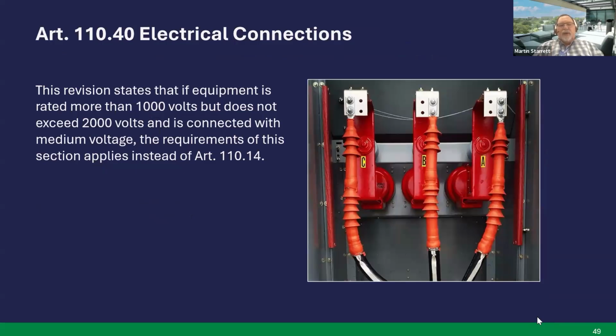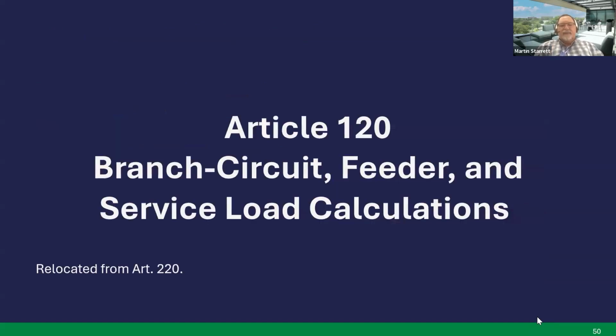Article 110.40, electrical connections. We already looked at 110.14, but 110.40 will apply if equipment is rated more than 1,000 volt, but does not exceed 2,000 volt and is connected with medium voltage. The requirements of this article apply instead of 110.14. Next slide, please.